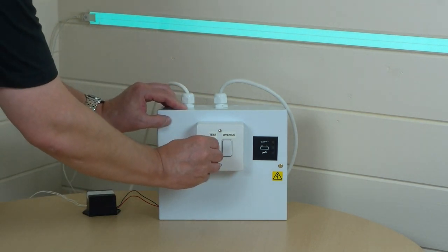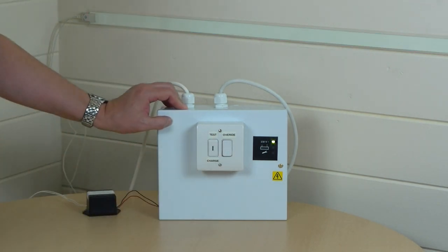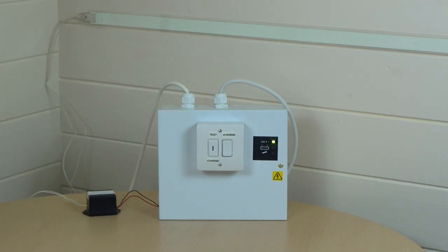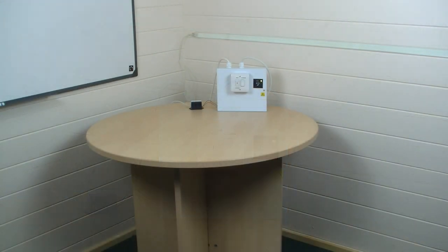We'll put that back to reset and now we can do a simulated mains failure. As you can see, we've zoomed out a little to allow us to see more of the actual room, and when I unplug the mains the Light tape comes on immediately.